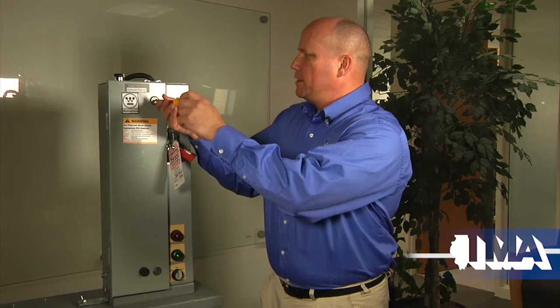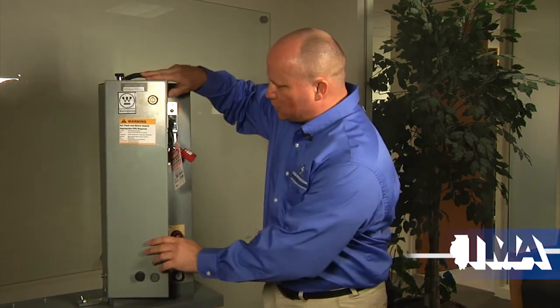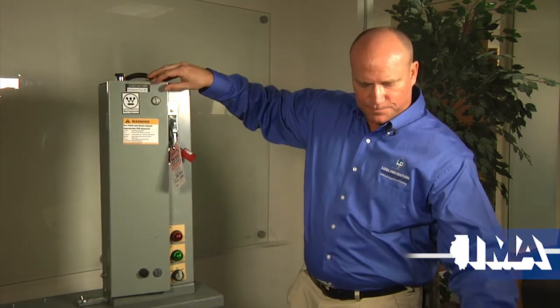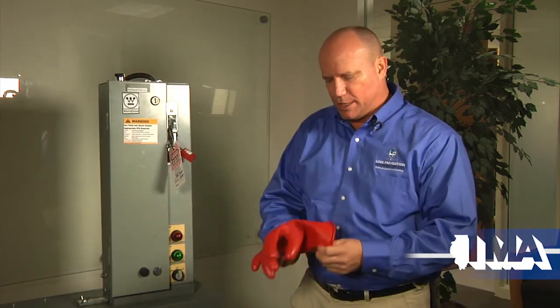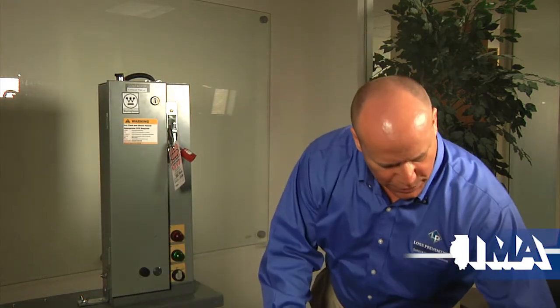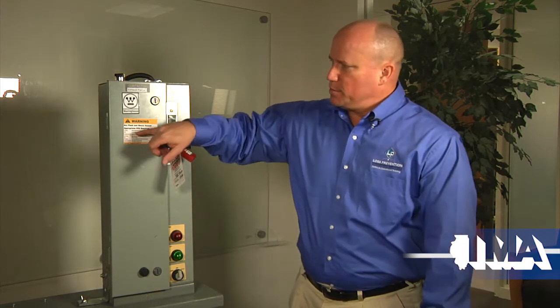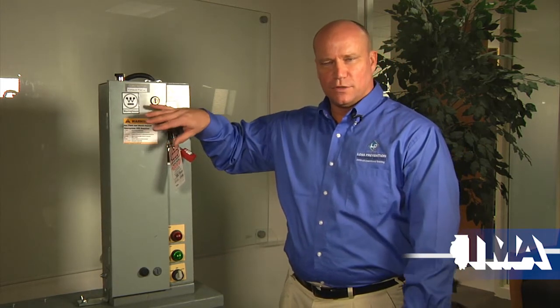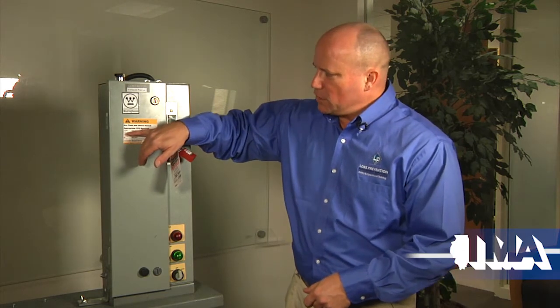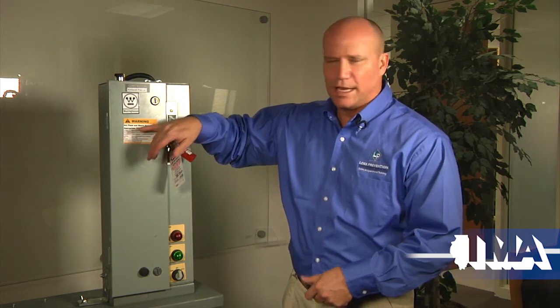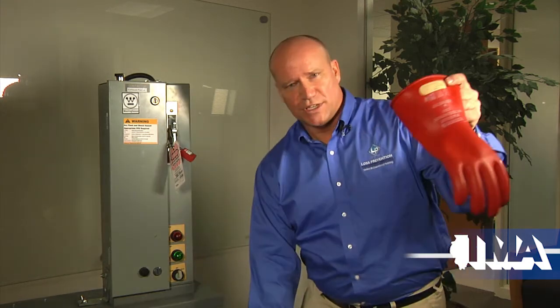In the slide, he's using an outlet. For me, it doesn't necessarily have to be. If you have a known voltage source in your work area, now I'm not going to go ahead and, actually, what I'll do is I'll go ahead and keep these on. I'll just show you what you need to put on in order to protect yourself. If you look at NFPA 70E and you look at the back of the tables, it'll say, based on the incident energy level, worst case of the equipment, and after the analysis has been performed, you'd go ahead and use that as a starting point. For me right here it is 0.09 cals per centimeter squared, which is a relatively low value. In the back tables, there is also a table that will aid to determine what articles of clothing are necessary for that. So for anything less than 1.2 cals, I would need rubber safety gloves.